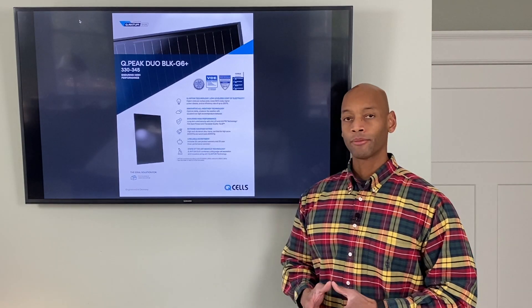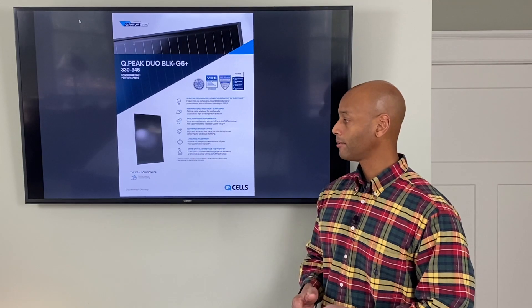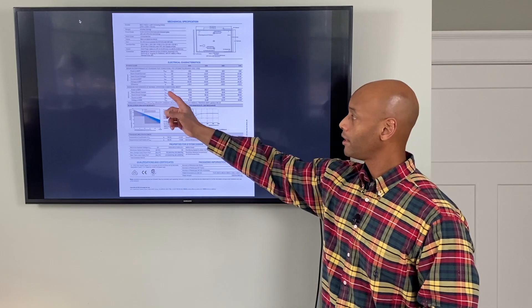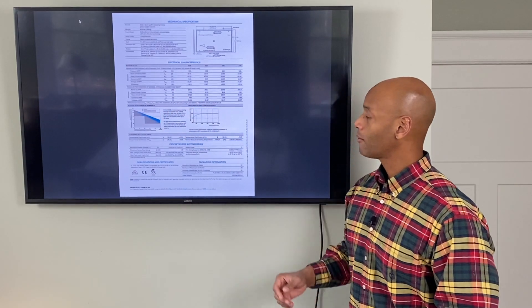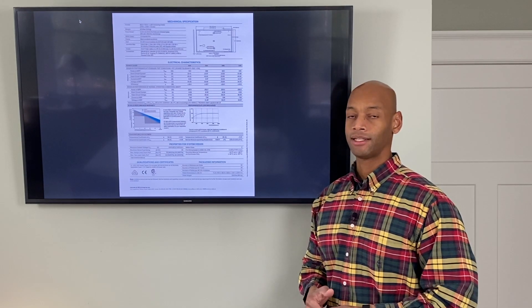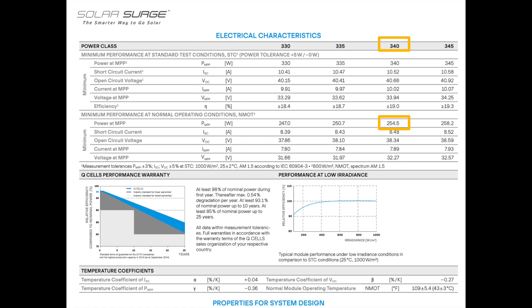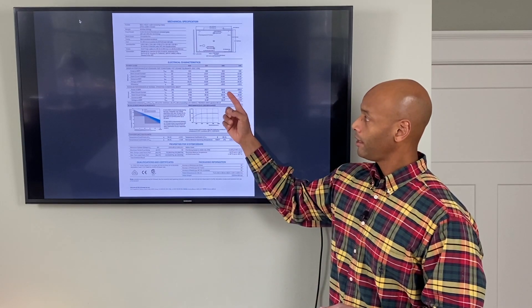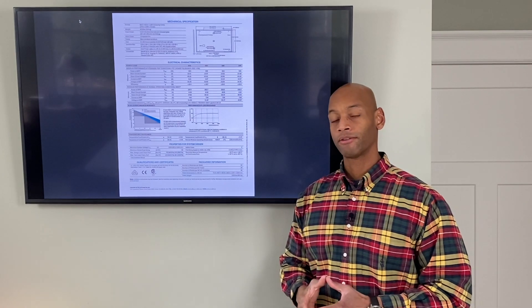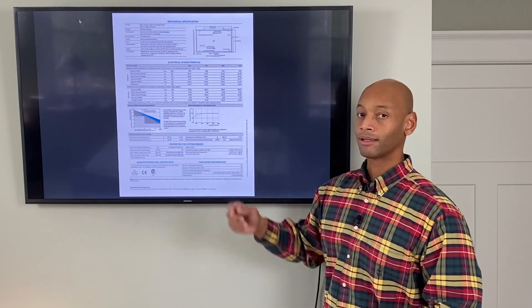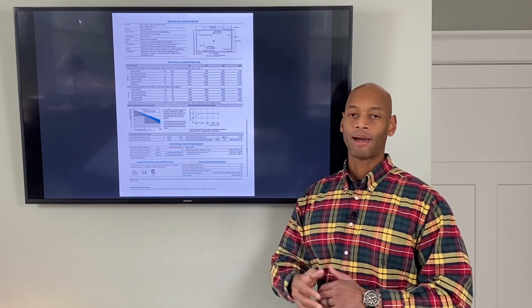The solar panel we're offering now is the Qcells 340-watt panel, and I want to show you the difference between the STC rating versus the NMOT normal operating conditions rating. When I say 340-watt, I'm referring to the STC standard test condition rating. For that model panel, the Normal Module Operating Temperature rating is only 255 watts — about a 90-watt difference. So although you might look at a 340-watt solar panel, in real-world conditions we're only going to get around 255 watts, which means we could pair it with an inverter more in line with that real-world power rating.